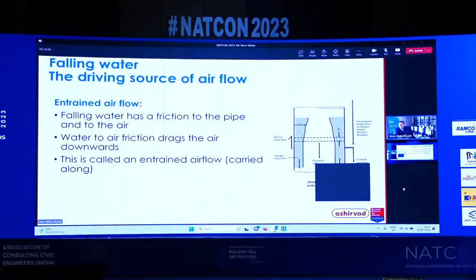And then if you're going to get into the maths, it's why the air is moving and the pressure is there. It's the frictional slip between the falling water and the air dragging forward, and this airflow is carried along with it. And if we don't replace that air, the pressure increases, and if the pressure exceeds a threshold of 40 millimeters water gauge, our water trap seals are at risk within the building.